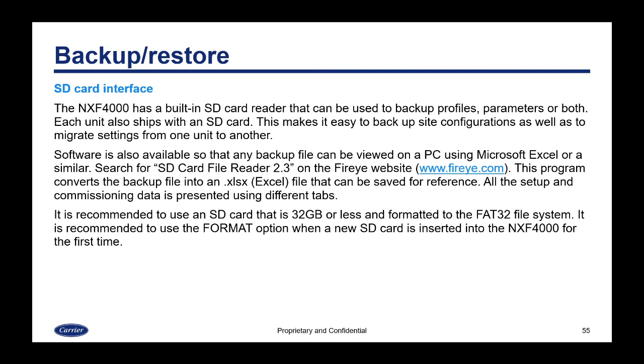And this program converts the backup file created by the NXF4000 into an XLSX, which is an Excel file that can be saved for reference. All the setup and commissioning data is presented using different tabs. When using an SD card, it is recommended that it is 32 gigabytes or less, that's what we use, and formatted to the FAT32 file system. It is also recommended that you use the format option with a new SD card, and then the NXF4000 can format it for you in the proper format.